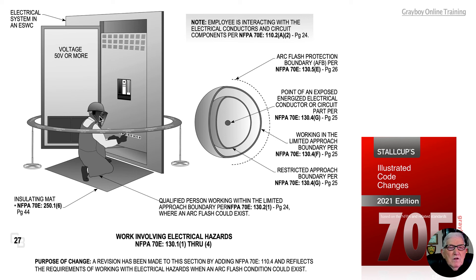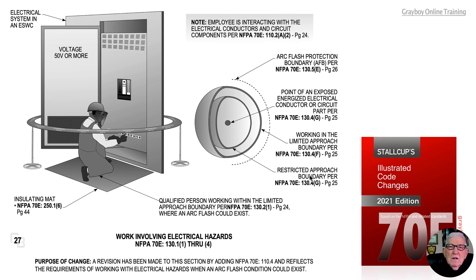Standing in the limited approach boundary — with the back of your head — you need your shock hood, your shield, your glasses, and so forth. The point of exposed energized electrical conductor circuit parts is when you're actually working on that part, either with an insulated tool or insulated gloves rated equal to or greater than the voltage. The restricted approach boundary is usually extending the protective arm with a protective tool, insulated glove, and so forth, to make contact with that component.